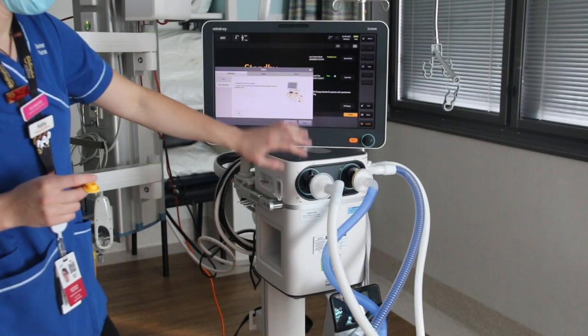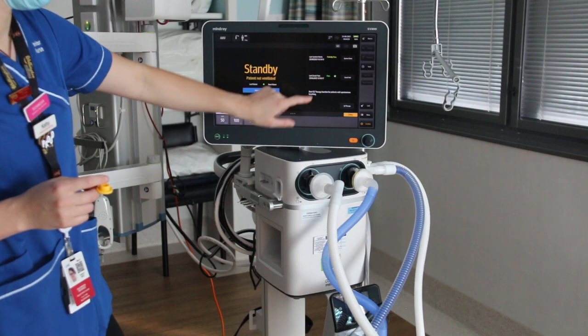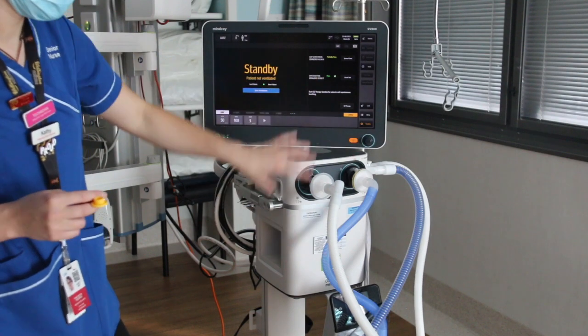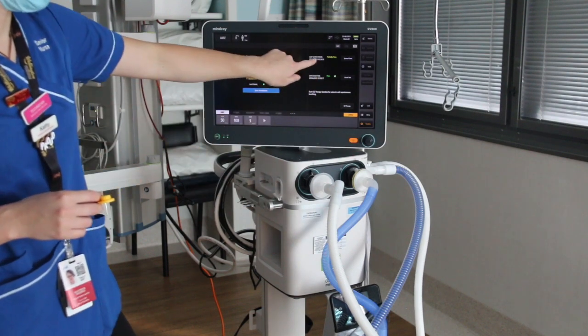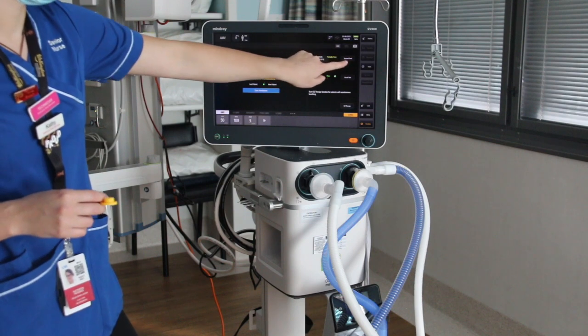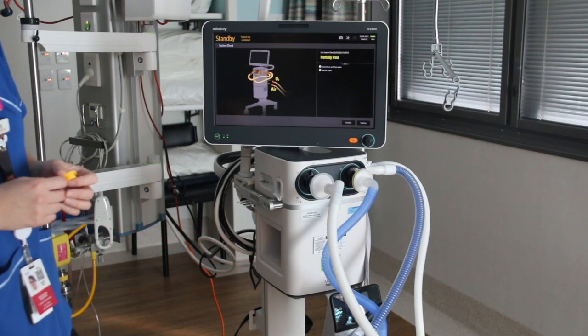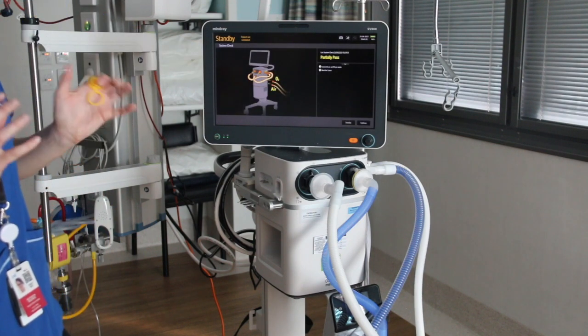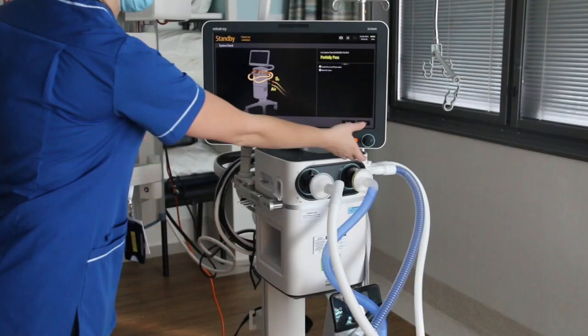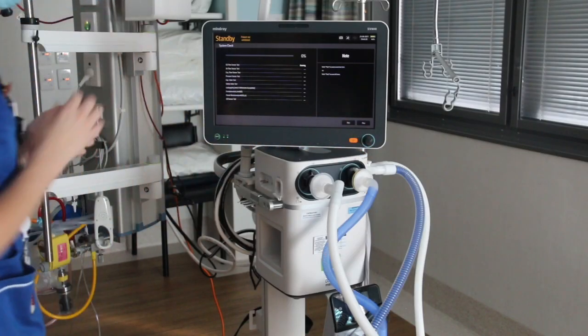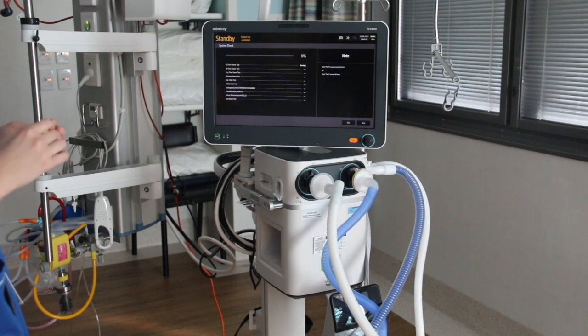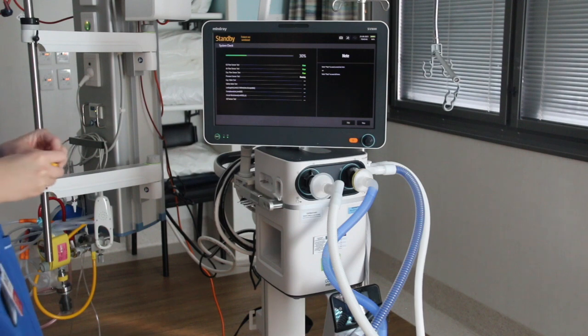Once you've done that and your flow sensor is happy, the next step to do is your tightness and your general system check. That option comes up here on the main screen, system check, and this test only takes about 2 minutes and is, as I say, checking the tightness. Once this calibration system check is finished, your ventilator is ready to use, provided it passes.